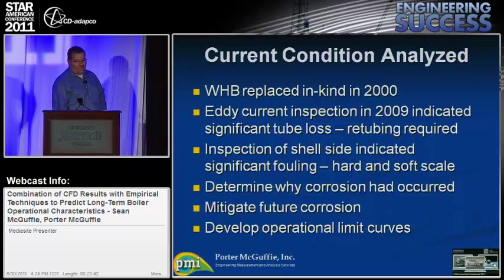The current condition that I'm really going to talk about today is a waste heat boiler that we did for a refiner client of ours. The waste heat boiler was replaced in kind in 2000, so basically they just swapped out a new waste heat boiler with the same design as had been operating since the early 80s.